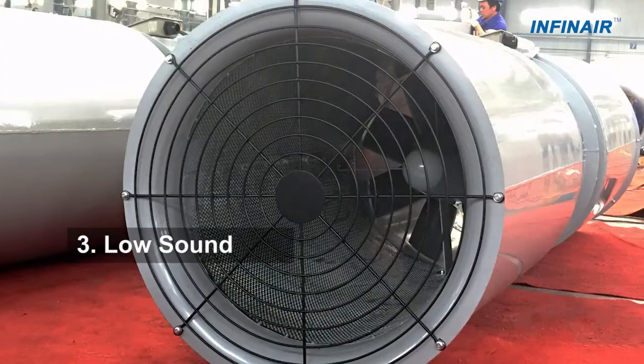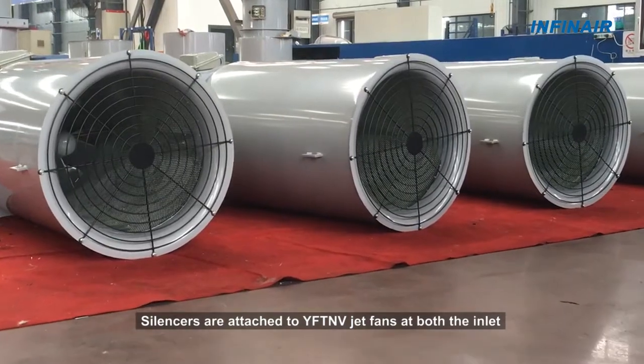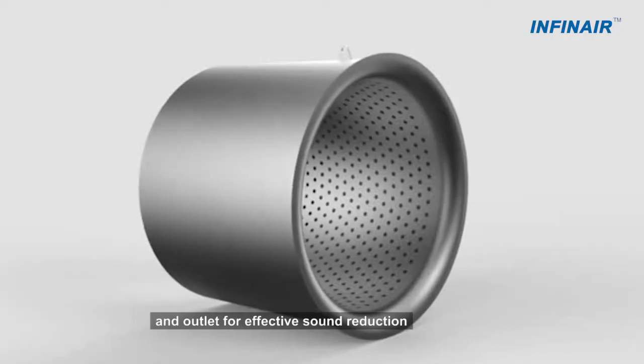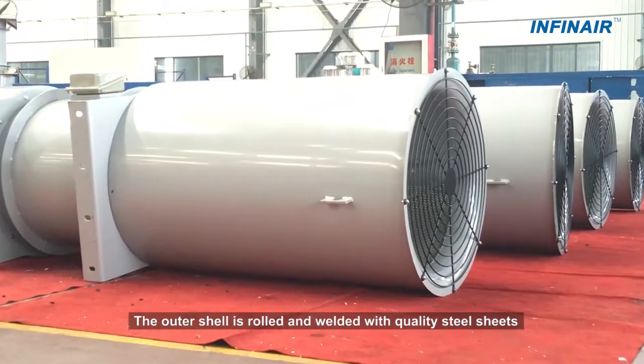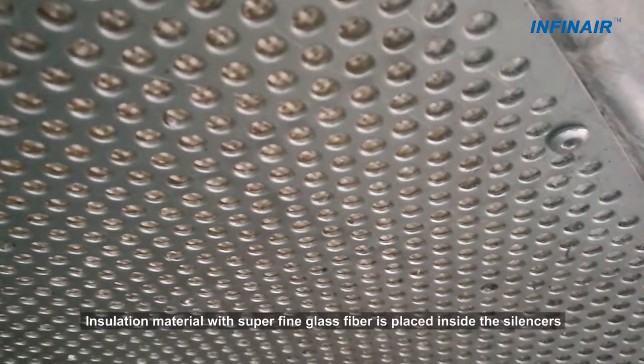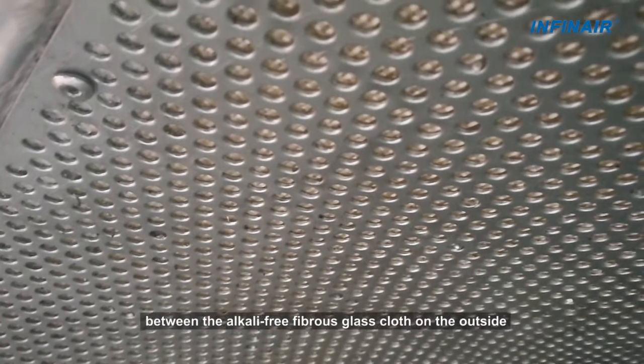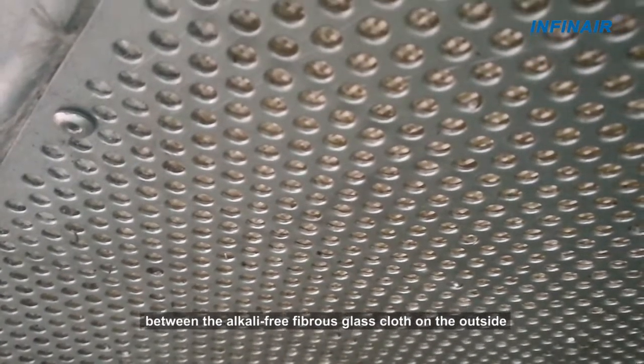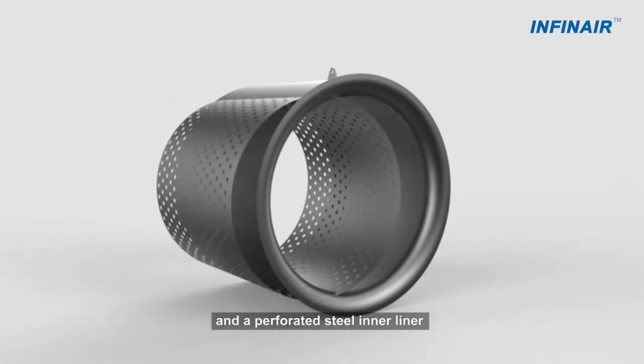3. Low Sound: Silencers are attached to YFTNV jet fans at both the inlet and outlet for effective sound reduction. The outer shell is rolled and welded with quality steel sheets. Insulation material with superfine glass fiber is placed inside the silencers between the alkali-free fibrous glass cloth on the outside and a perforated steel inner liner.